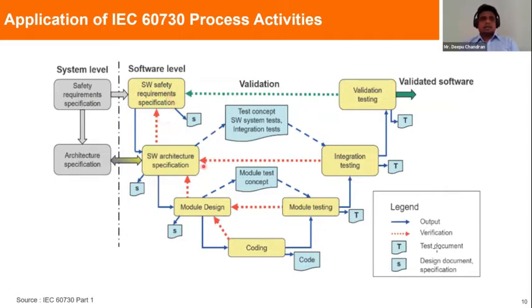When you look at a generic V model, the additional activity is indicated by the red colored arrows, which shows that you need to start your verification activity right at the requirement stage itself. As soon as the functional and safety requirements are available, verification needs to be done, which includes reviews as well as establishment of traceability.